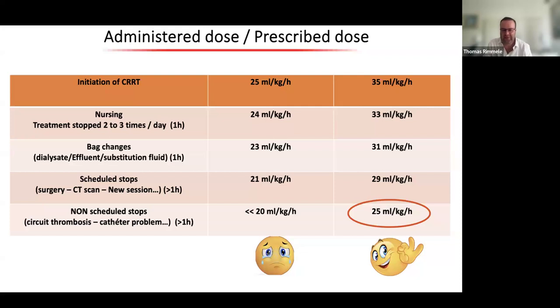Now on the new machines you have the safety mode, with only the blood pump running, but not the effluent pump, for example. So I'm losing a little bit of dose. During every change of the bags, I'm losing a little bit of dose. If my patient goes to the operating room for surgery, I'm going to lose a little bit of dose. CT scan, if I start a new session, if I have a catheter problem, I will lose some dose, right? If there is thrombosis. So if I prescribe 35, I'm going to get 25 ml per kilo per hour to my patient.